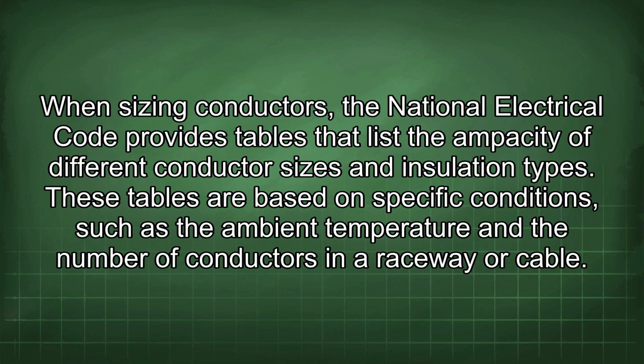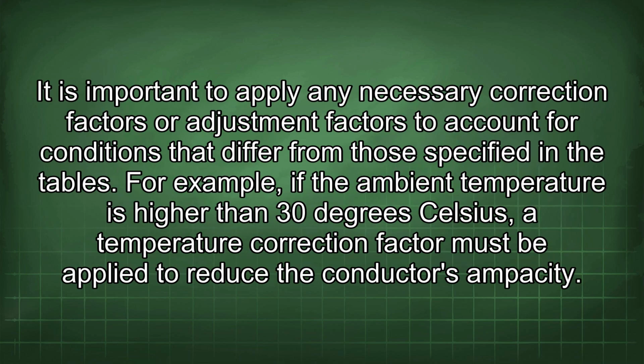When sizing conductors, the National Electrical Code provides tables that list the ampacity of different conductor sizes and insulation types. These tables are based on specific conditions, such as the ambient temperature and the number of conductors in a raceway or cable. It is important to apply any necessary correction factors or adjustment factors to account for conditions that differ from those specified in the tables. For example, if the ambient temperature is higher than 30 degrees Celsius, a temperature correction factor must be applied to reduce the conductor's ampacity.